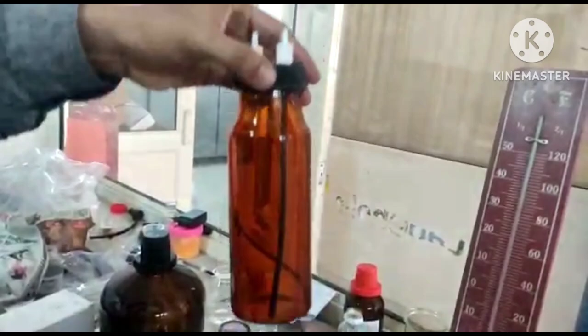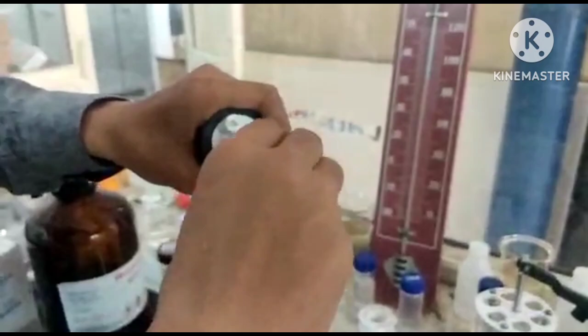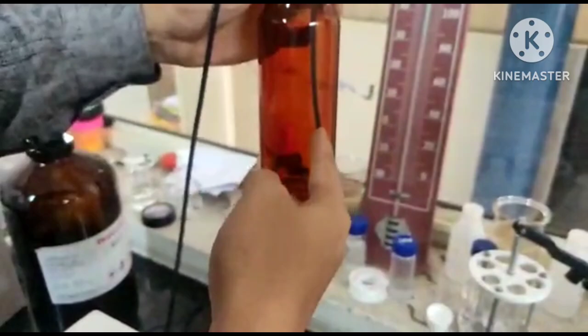Thereafter, what we have to do on the back. On the back we have two pipes. One is input and one is output. The input one we have to connect with the reagent bottle. So the reagent bottle should be connected to the nozzle which is connected directly with the inner pipe. With the same we have to connect the input line. So we have to connect it here. As you can see, now I have connected the input pipe with the same pipe which is going inside with the same nozzle. So you have to connect it like that.